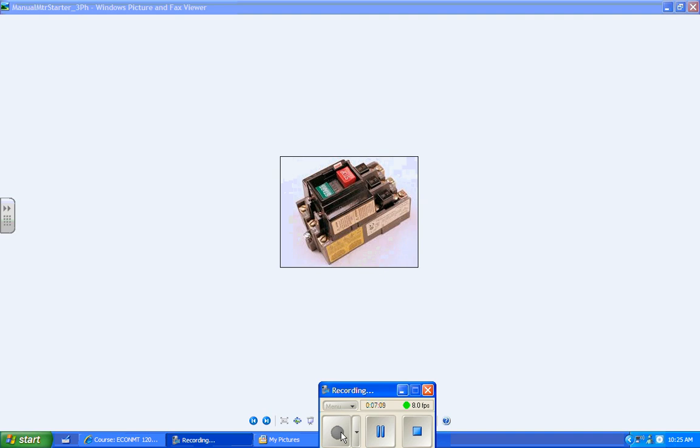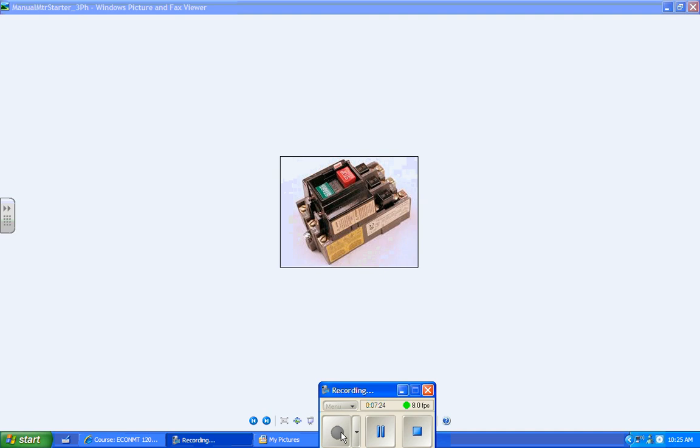But it can be configured so that it does, and to do that you need to add a solenoid so when the power drops out it opens the switch. So there is a specialized manual motor starter that will open up and give you low voltage release. But generally speaking, manual motor starters do not have low voltage release. If the power goes out, the motor will stop, but when the power comes back on it will restart without any instructions from you.